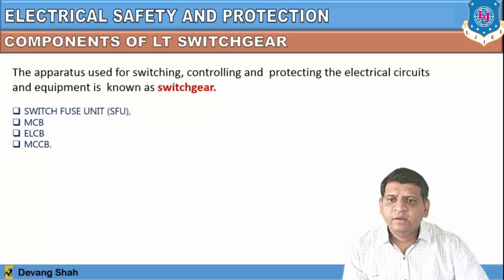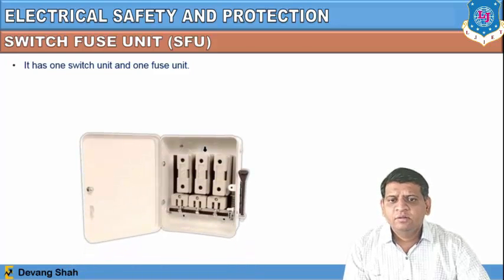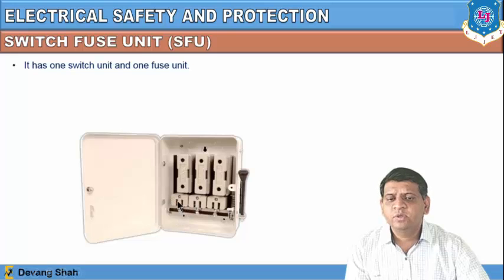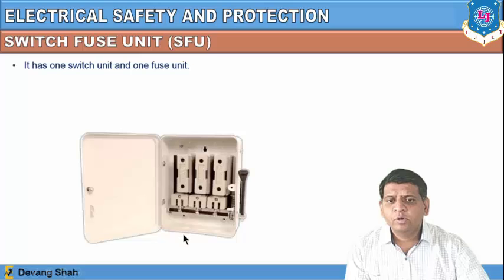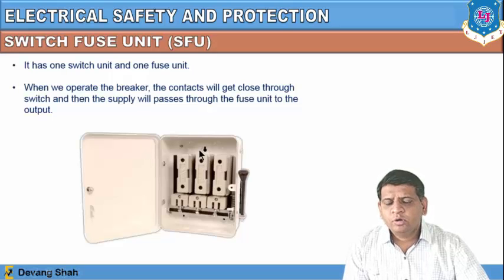The components of LT switchgear include switch fuse unit (SFU), MCB, ELCB and MCCB. The switch fuse unit is a combination of one switch unit and one fuse unit. The line coming from outside goes to the switch and then to the fuse system. When we operate the breaker, the contacts close through the switch and supply passes through the fuse unit to the output, protecting the output circuitry.